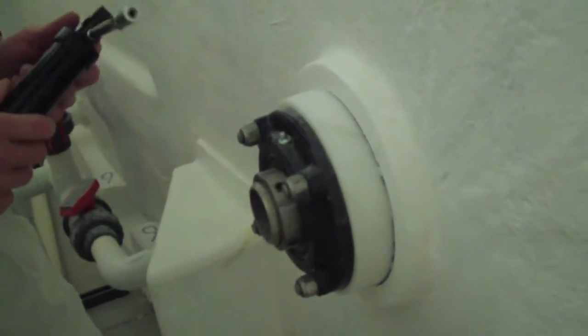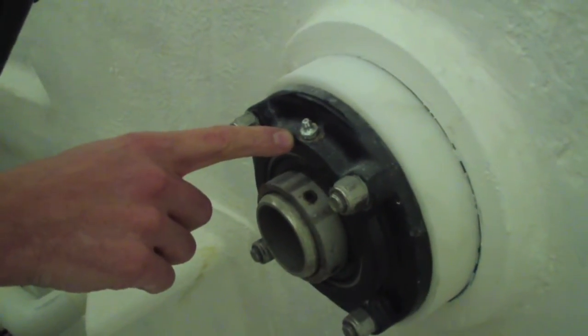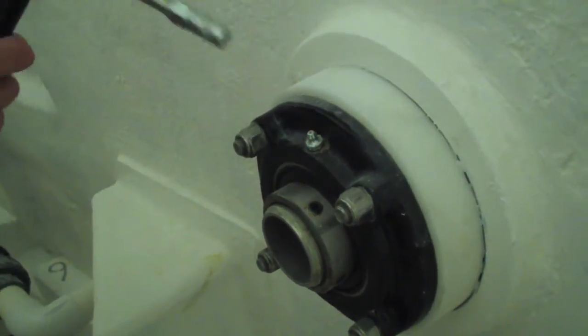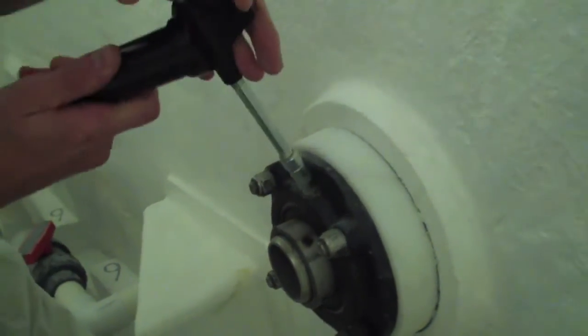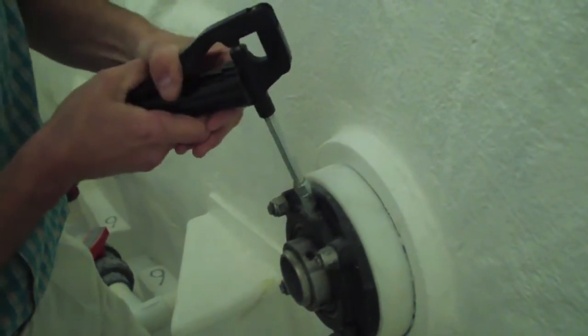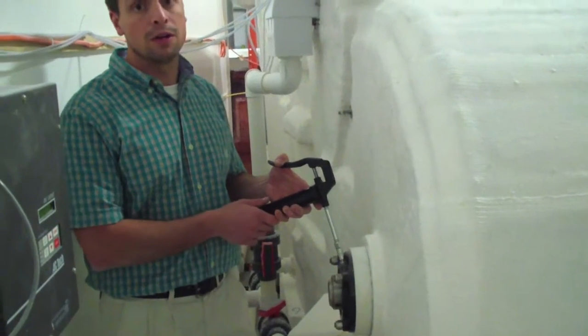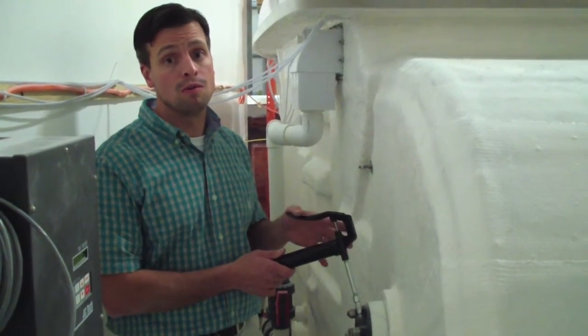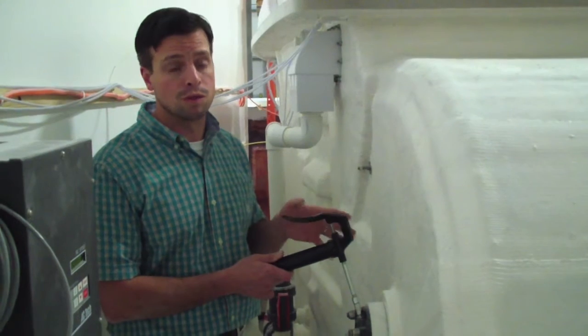So it's a standard Zerk fitting just like you'd see on a lawn mower. Here's your Zerk fitting on the paddle wheel bearing. We'll take our grease gun, make sure we get a good connection. One, two. And there you go, two squirts of grease and you're all set. There's no need to over grease. You only want to do two squirts once a year.